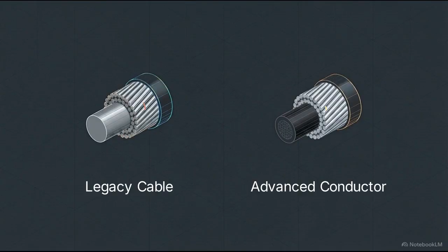To solve the inertia problem, operators must deploy grid-forming inverters. These are advanced computers paired with batteries that actively generate local voltage and synthesize the physical momentum lost by retiring coal plants. Bypassing the grid's physical constraints requires re-engineering both the thermodynamics of its cables and the electromagnetics of its frequency.